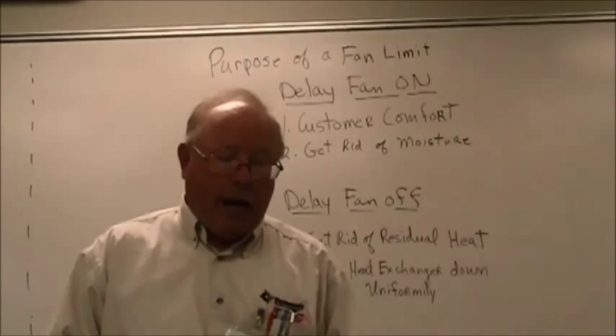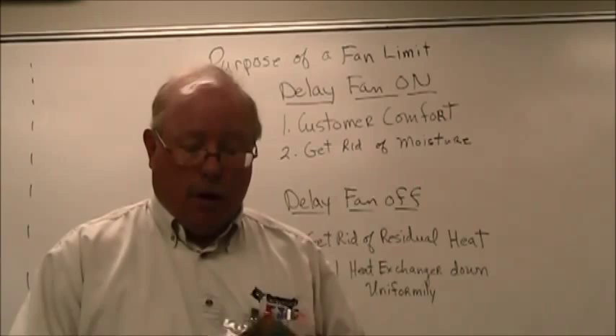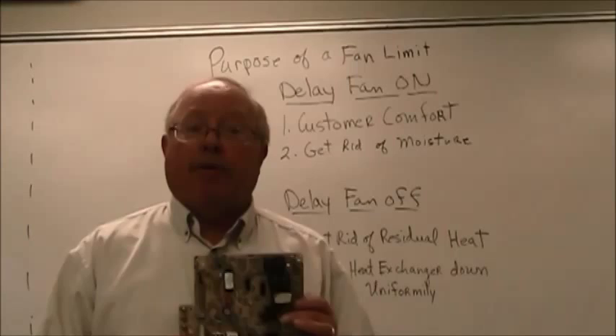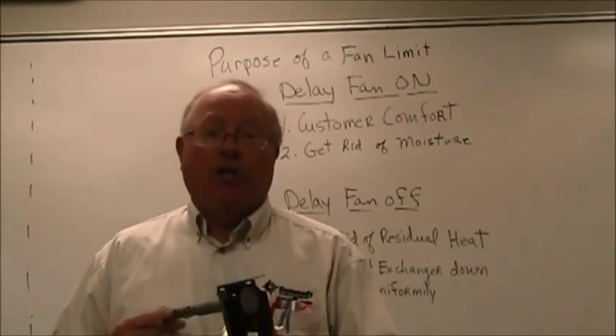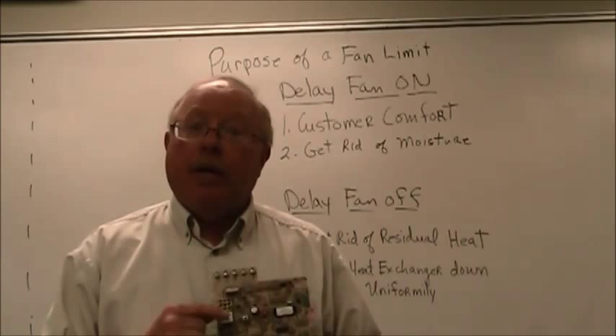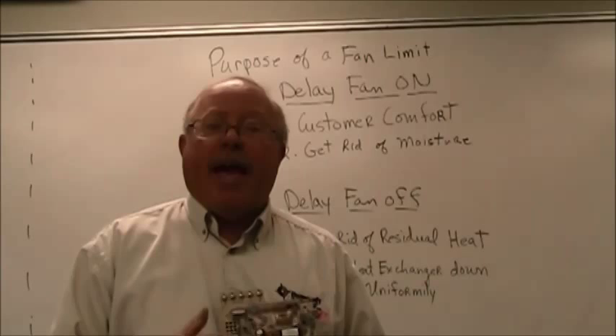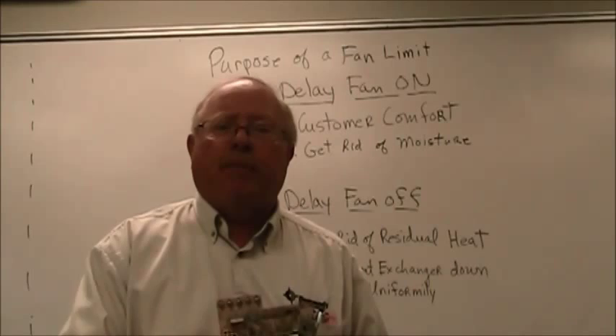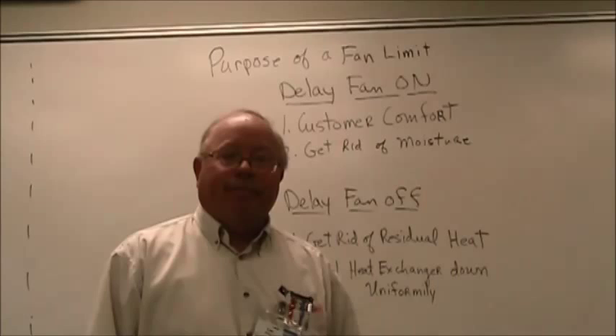That's the fan limit control — that's the purpose of the fan limit. Just a little reminder: since this is older technology, the newer technology is now the PC board, sometimes called an integrated fan control board. In this older situation, temperature turned the fan on and temperature turned the fan off. With our new PC boards — printed circuit boards found inside the furnace — the fan is now turned on by time and turned off by time. By the way, the fan on time is not adjustable, but the fan off time is adjustable, usually anywhere from 90 to 240 seconds. Two-minute tutor, out.